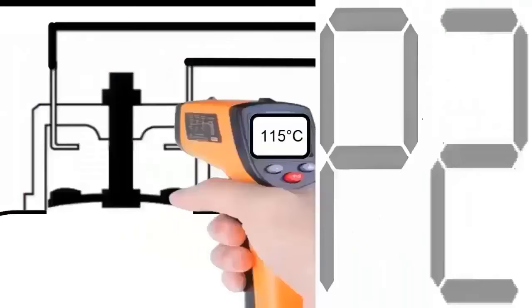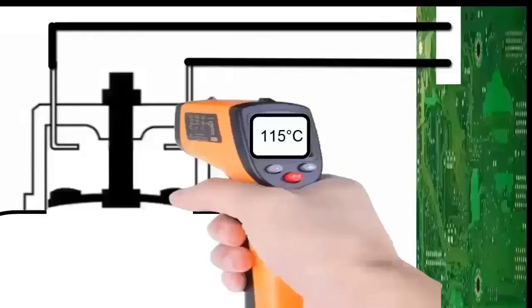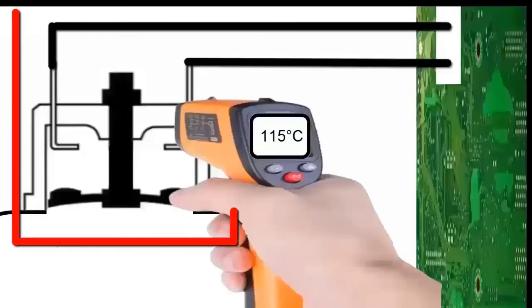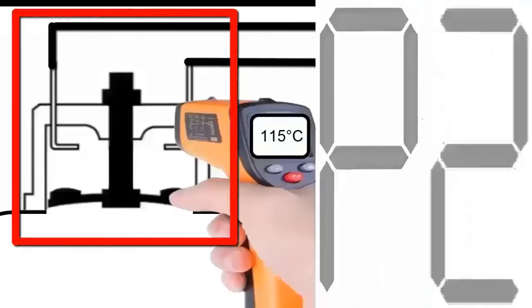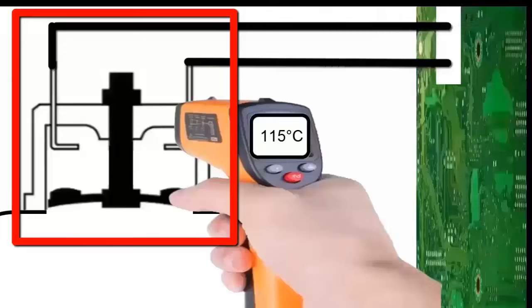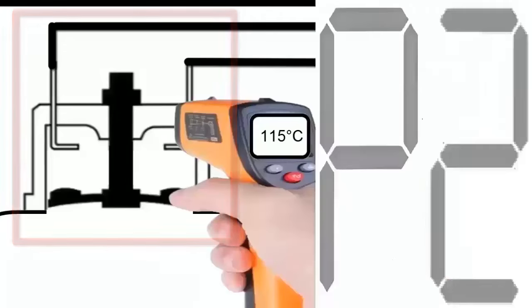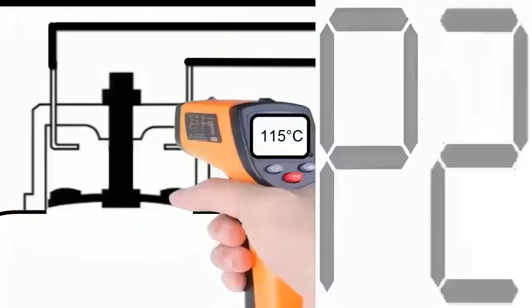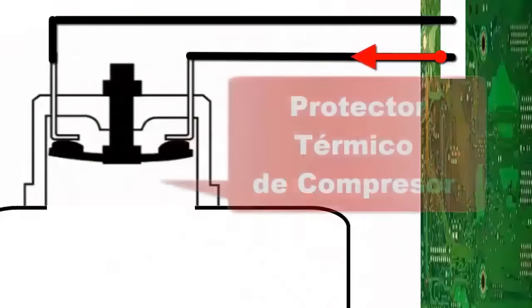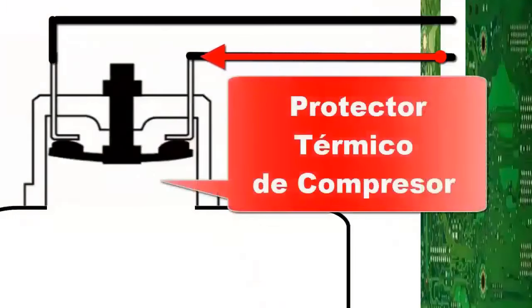6. False overload alarm. If the current measured in step 1 is normal, the system might be detecting a false overload alarm. In this case, there could be an issue with the compressor overload switch. Try temporarily bypassing the switch to see if the error disappears.